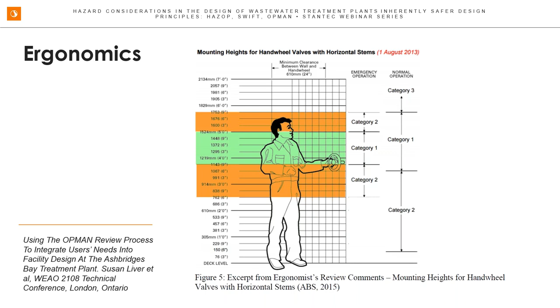Now the hand wheel's too close to the wall. Every time they turn it, if they don't have gloves on, they're going to skin their knuckles. If we look at valve number 2, the hand wheel is too high, so they're going to have to reach up to close that valve. That's not a good ergonomic situation.